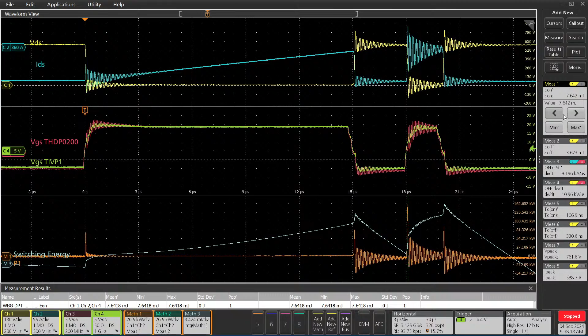So if we want to dive into the measurements and their results, note that the energy on measurement and all of the other double pulse measurements along the right-hand side are now pre-populated. If we single click on our energy measurement and single click onto this particular badge, you'll notice we've zoomed in on the turn on pulse of the second event.